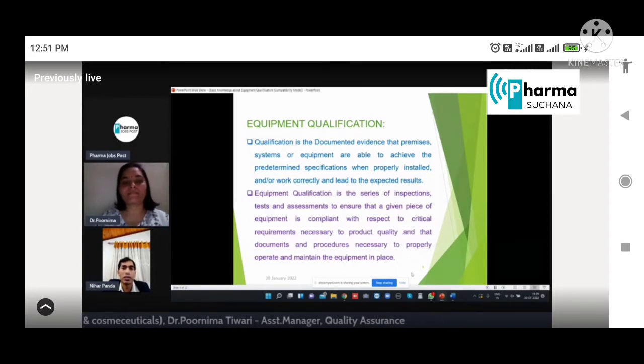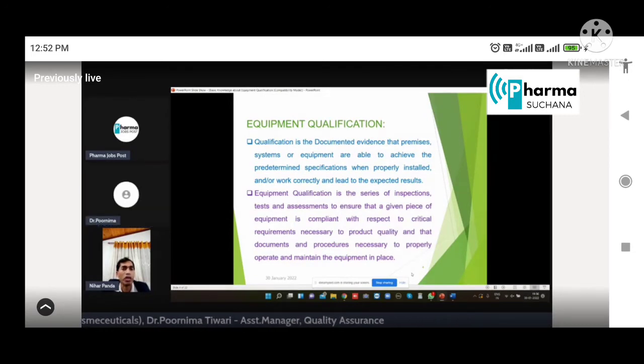Basically, what is qualification? Qualification is documented evidence. Whatever documented evidence is related to qualification, you have to complete, like DQ, IQ, OQ, and PQ. Qualification is the documented evidence that premises, systems, or equipment are able to achieve the predetermined specifications. What are the predetermined specifications? Those are the URS: what is our requirement towards the equipment, the facility, or the system, when properly installed and working correctly, leading to the expected results. After qualification, we should get the expected results which are predetermined as per the URS.